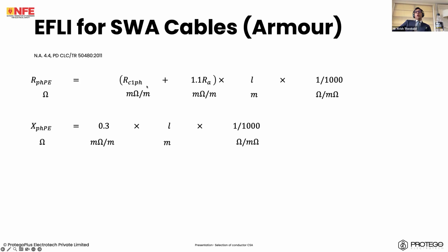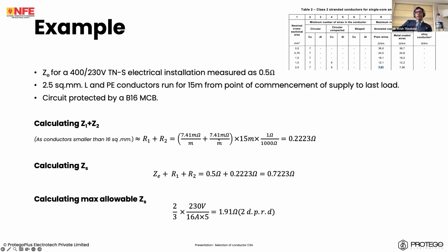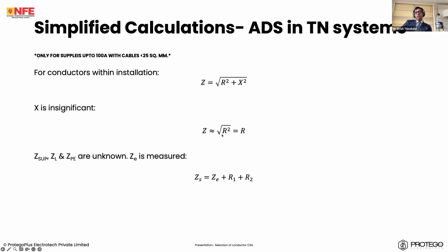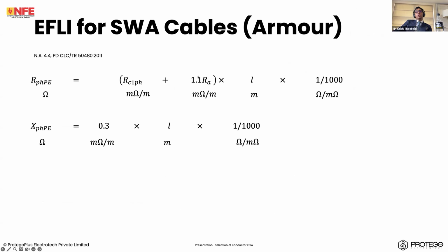I'm repeating. Earlier, we did R1, R2, but they were both copper conductors. So we just did 7.41 plus 7.41. If the armor is used as a protective earth conductor, you cannot do 7.41 plus 7.41. You have to do 7.41 plus whatever this value is for the armoring. I'll show you an example calculation. And we multiply this value by 1.1. Multiply by the length, simple. The reactive component we assume as 0.3 milliohms per meter. Multiply by the length, multiply by the correction factor just to convert from milliohms to ohms.